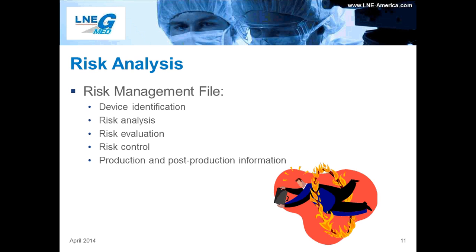Okay, risk analysis. Let's talk about risk management. When submitting your risk analysis, you should include a full risk management file. The risk management file should include identification of the device, the risk analysis, risk evaluation, and any control measures, production and post-production information.